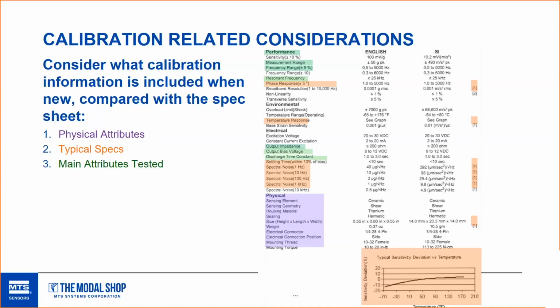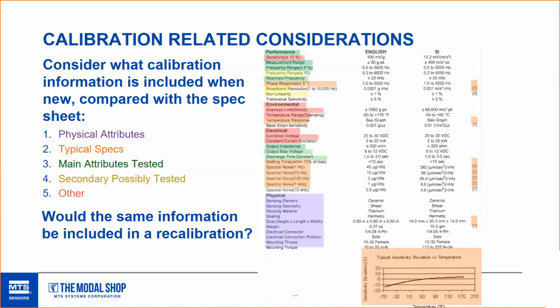What you're really looking for are the main attributes. Are they tested when you're getting your recalibration done? The overall sensitivity, the measurement range, and then the secondary specs also tested. Your resolution, nonlinearities, things like that. And then if things are important to you for other specs that are also important, it's kind of important to know from your cal provider what they're going to provide and what's important to you. I feel like some of the highlighting got off a little bit here, but in general. So would that same cal information be included in your recal? Ask yourself that, because that's part of your risk assessment. If it's acceptable, if it's not included.